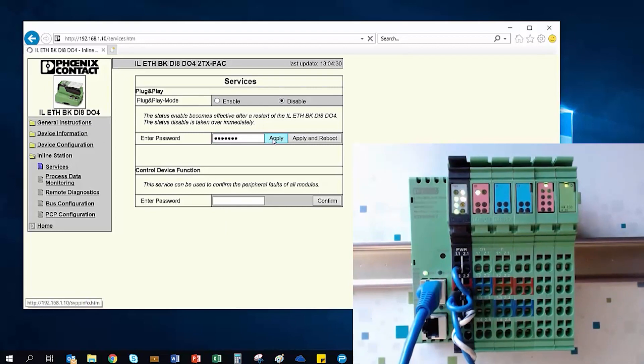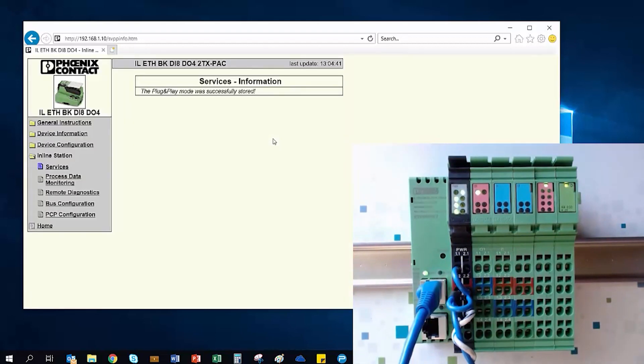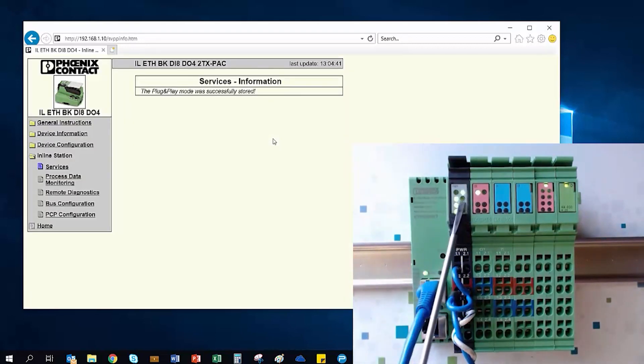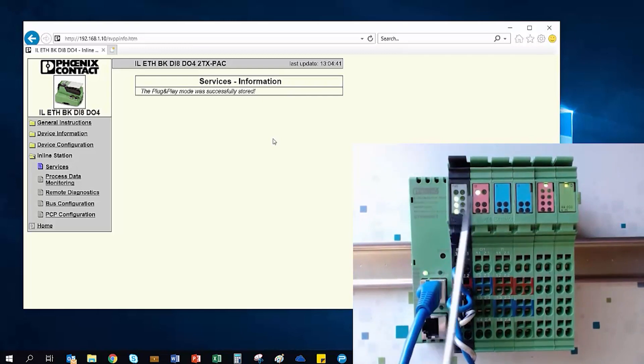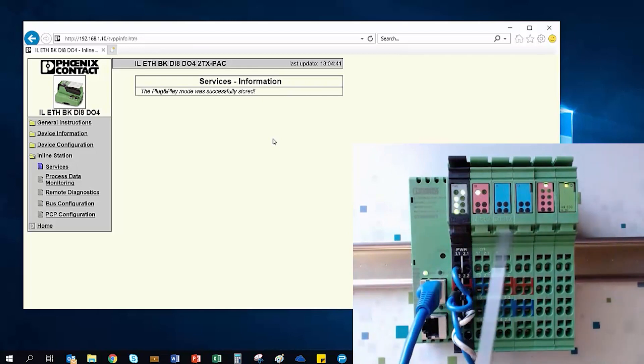As soon as I apply the setting changes, you'll notice that the bus coupler's PP light goes out, indicating that we're no longer in that mode and that we are now permanently holding the current bus configuration in the bus coupler's permanent memory.